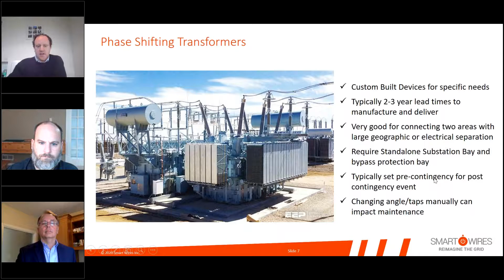Other power flow control solutions that have been installed again for the last 50 or 60 years are series capacitors and series reactors. Unlike the phase shifter, they actually impact the reactance of the line component of your power flow control equation. And in effect, what they do is inject a voltage at 90 degrees to the line current, which synthesizes a change in line reactance. So as a series capacitor will reduce your line reactance, it reduces the denominator in the power flow control equation and increases your power flow. And on the flip side, a series reactor will increase your denominator there, which will reduce your power flow on the circuit.